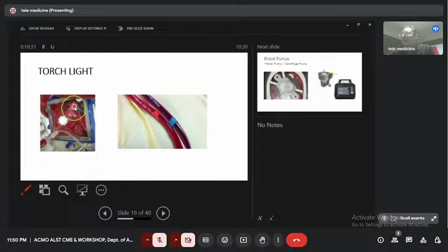Second, shine your torch over the oxygenator just to see if there are clots. If you are active enough, you can see the delta P - the difference pre and post - will show the pressures are increasing. Before that, if you have a torch light, you can see clots forming. By afternoon or evening, the delta P is going to increase.